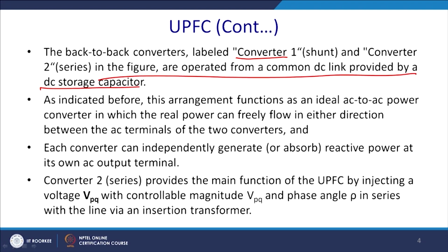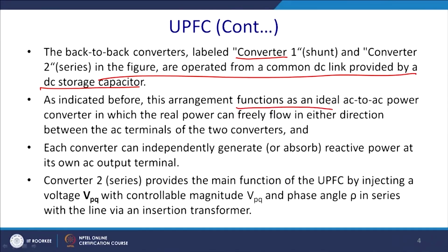So, the instantaneous difference of the power has to be fed through the DC link. As indicated before, the arrangement functions as an ideal AC to AC power converter in which the real power can freely flow in either direction between the two AC terminals of the converter, and each converter can independently generate or absorb reactive power at its own AC output terminal.